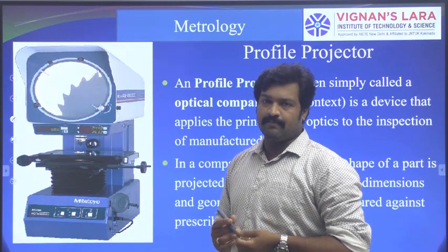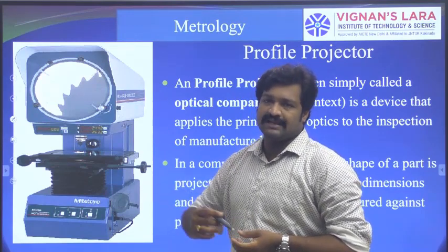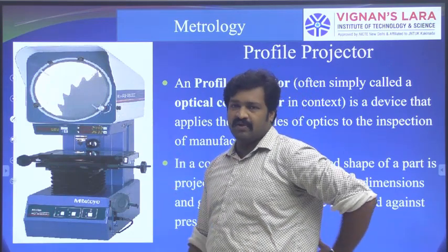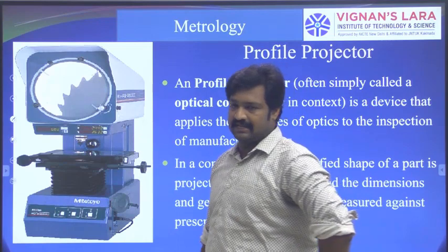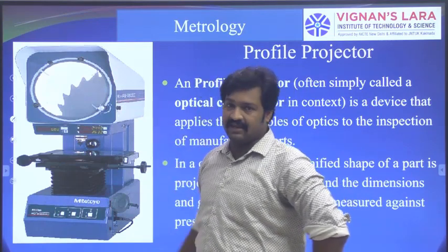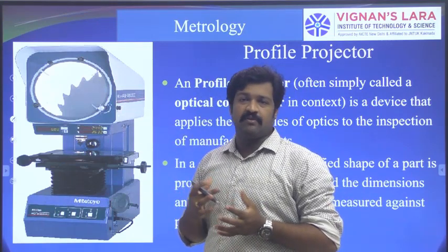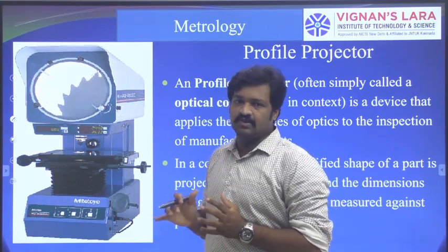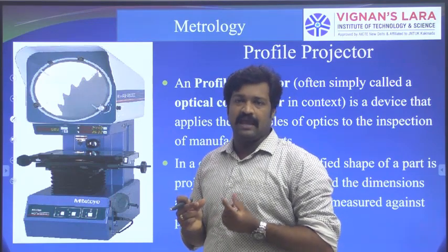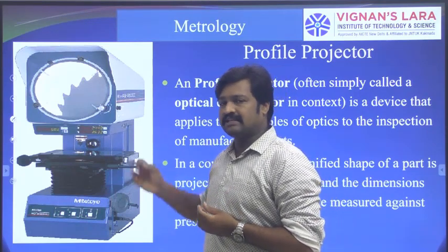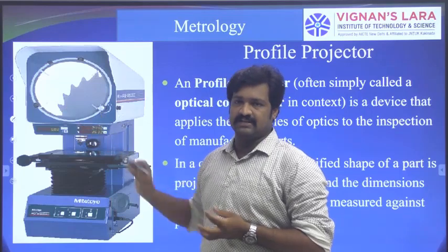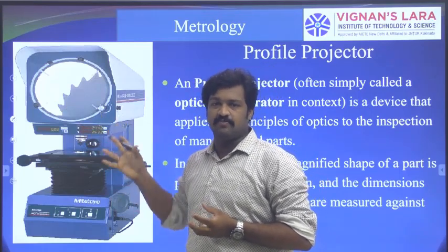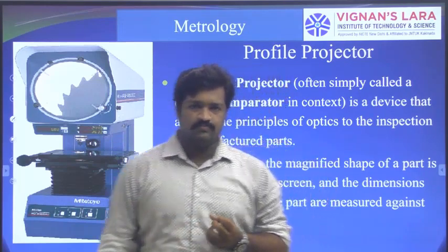The main difference between the tool maker's microscope and this profile projector is the screen. The profile projector consists of an optical screen, whereas in the tool maker's microscope, the component is viewed through an eyepiece. Apart from that, everything is the same. The main purpose of the screen is to magnify even the smaller components.